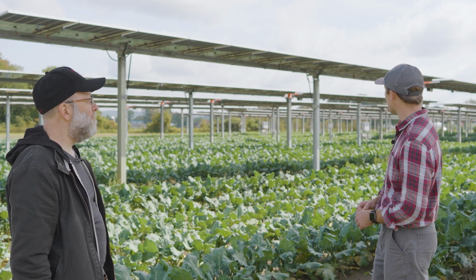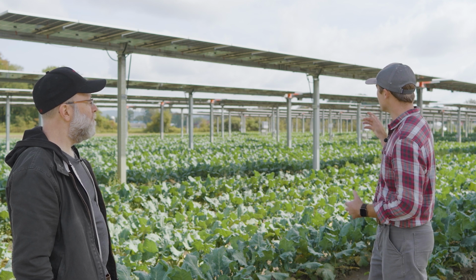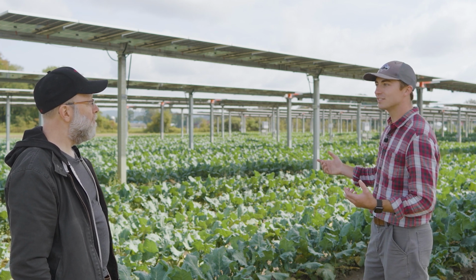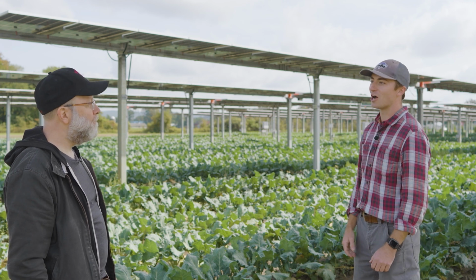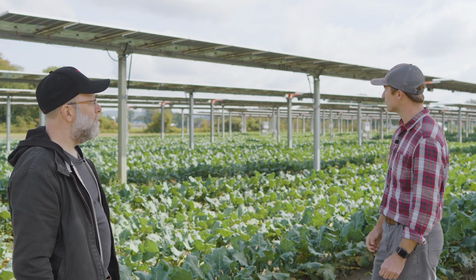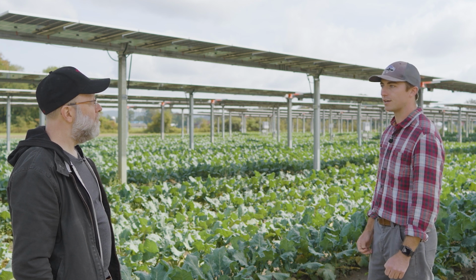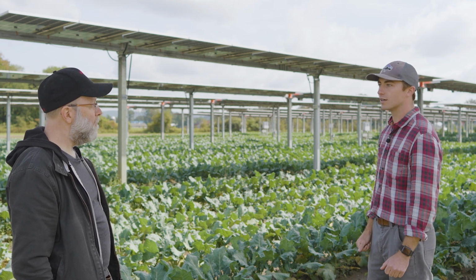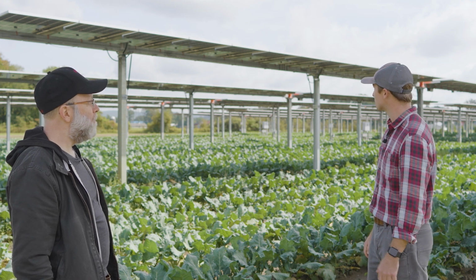And on that point of having the different motors, there's potential chance for greater outages with the motors, but if there is one outage, it doesn't hold up the rest of the system. The rest is still operating. So that was part of our design criteria when we were talking with different vendors. We ultimately went with a Solar Flex Rack S-Series product. And so far, it's been great to work with.